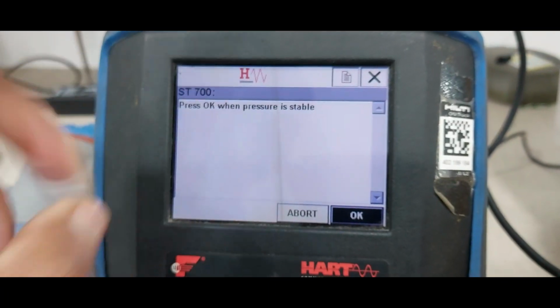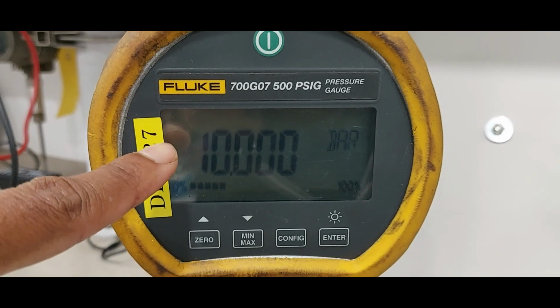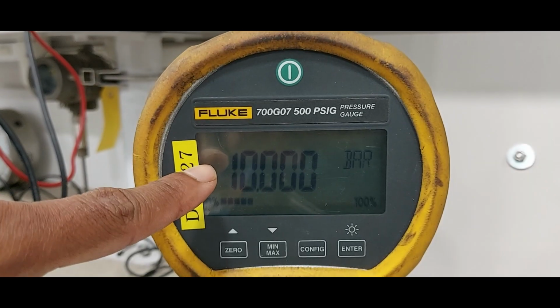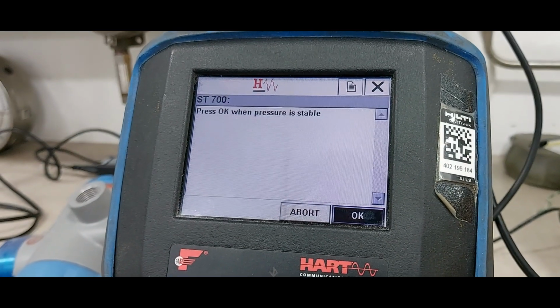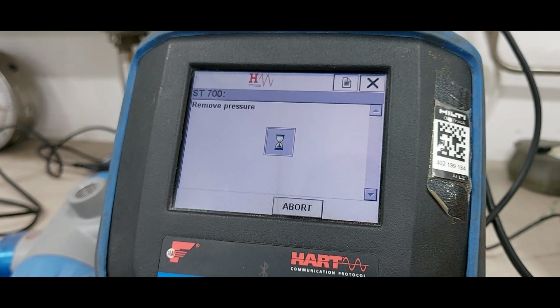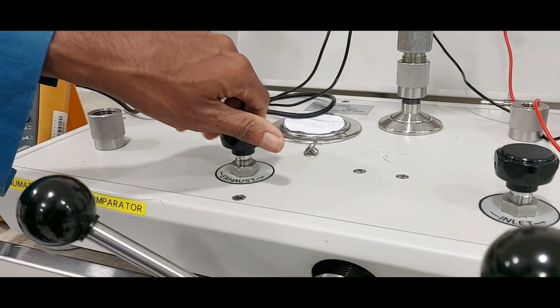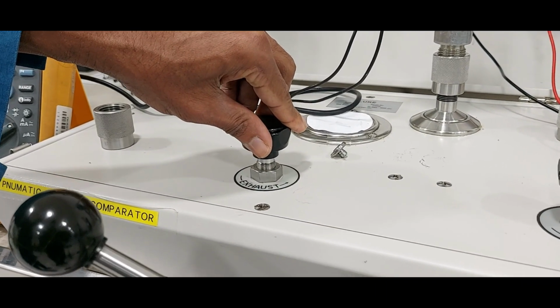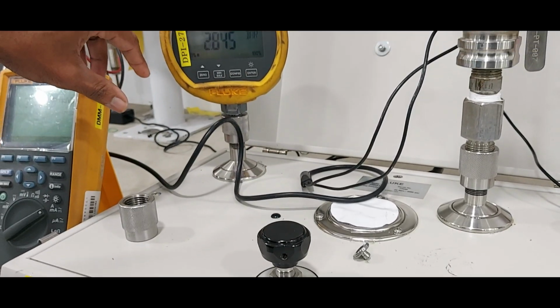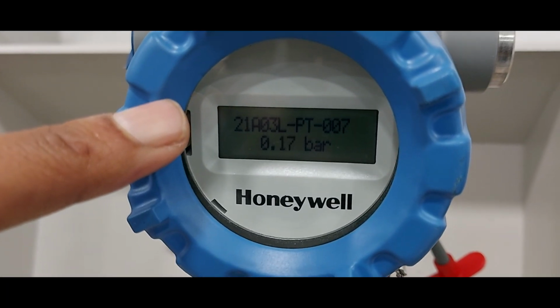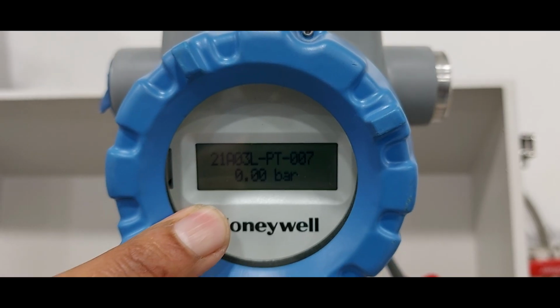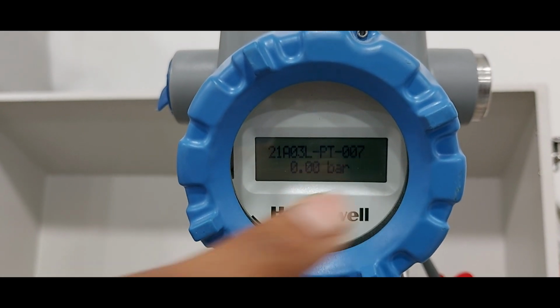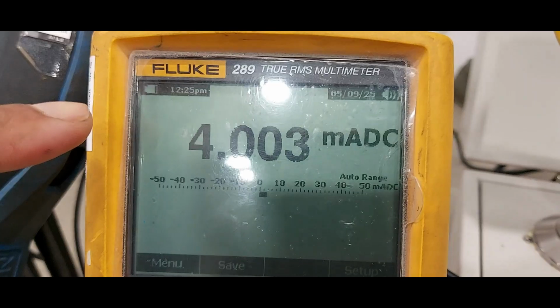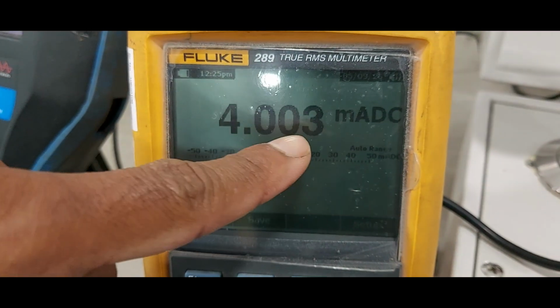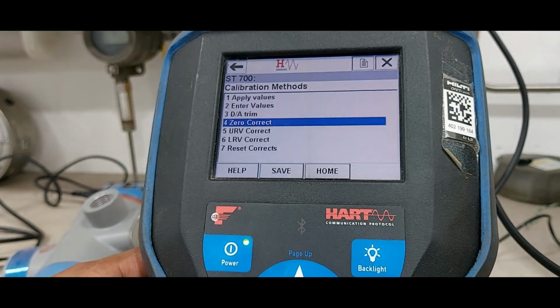Okay. Pressure is stable. Now pressure is stable condition. Reference gauge also showing stable condition. Now press OK. And remove the pressure from the unit. Slowly remove the pressure. Transmitter pressure is showing 0. Reference pressure also showing 0. Output is showing 4.003 mA. Okay, pressure calibration is completed.